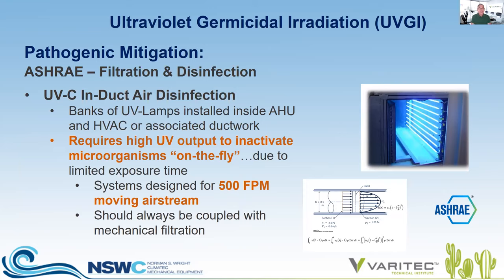ASHRAE's Epidemic Task Force states that banks of UV lamps installed inside air handlers or associated ductwork is certainly a recommendation. However, using UV light in an on-the-fly application requires more UV dosage than simply keeping surfaces in the direct line of sight of a UV generator free of microorganisms. General design considerations: best if you can maintain velocity of about 500 feet per minute or less. We can design for higher velocities up to 1,000 feet per minute, but the faster the air, the higher the dosage required. This is a calculation that can be effectively applied once we know the design parameters.